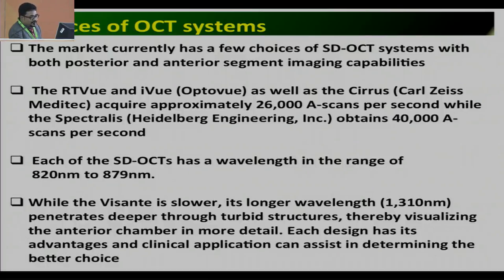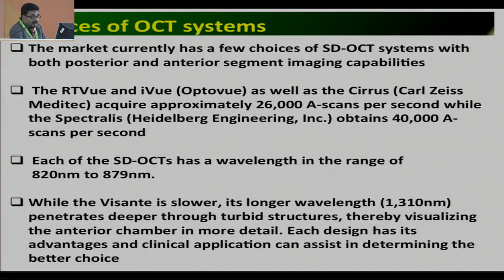Each of the spectral domain OCTs has a wavelength of 820 to 879 nanometers. While the time domain OCT is slower, its longer wavelength of 1310 nanometers penetrates deep through turbid structures, thereby visualizing the anterior chamber in more detail. Each design has its own advantages, and clinical applications can assist in determining the better choice.